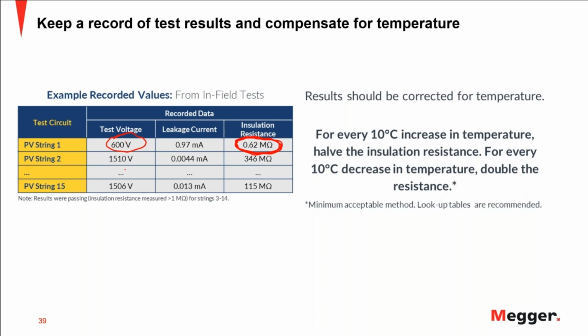So in some situations, I've seen that this value here is, I don't know, 2 megaohms, but the voltage is 600 volts when I intended to apply 1500 volts. So the 2 megaohms is a passing result, but the voltage didn't build up, and that is an indication that there's a problem in the insulation. So not only the resistance value, but also the voltage at the end of the test is very important.